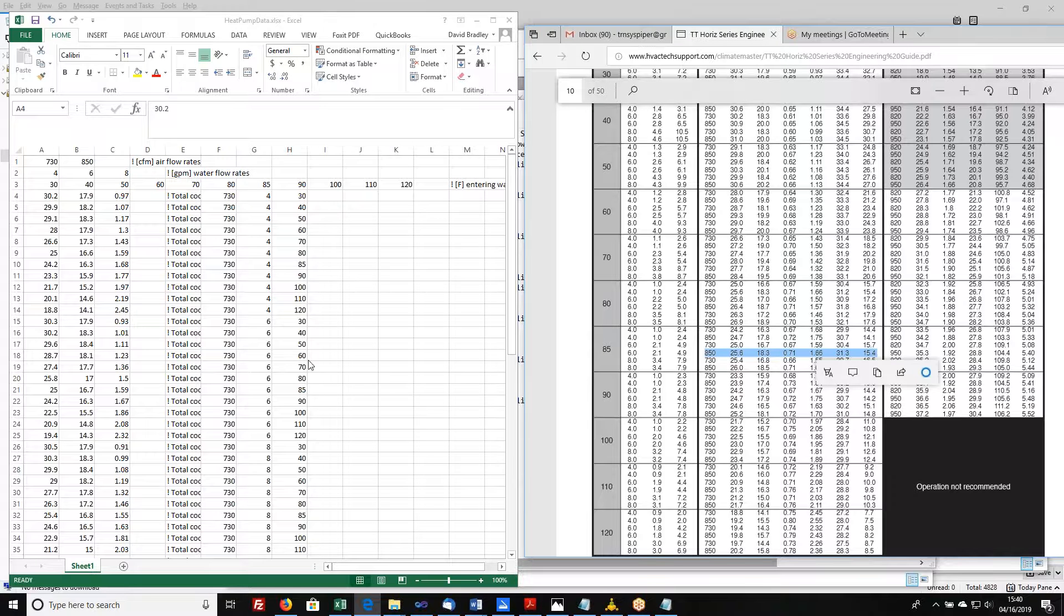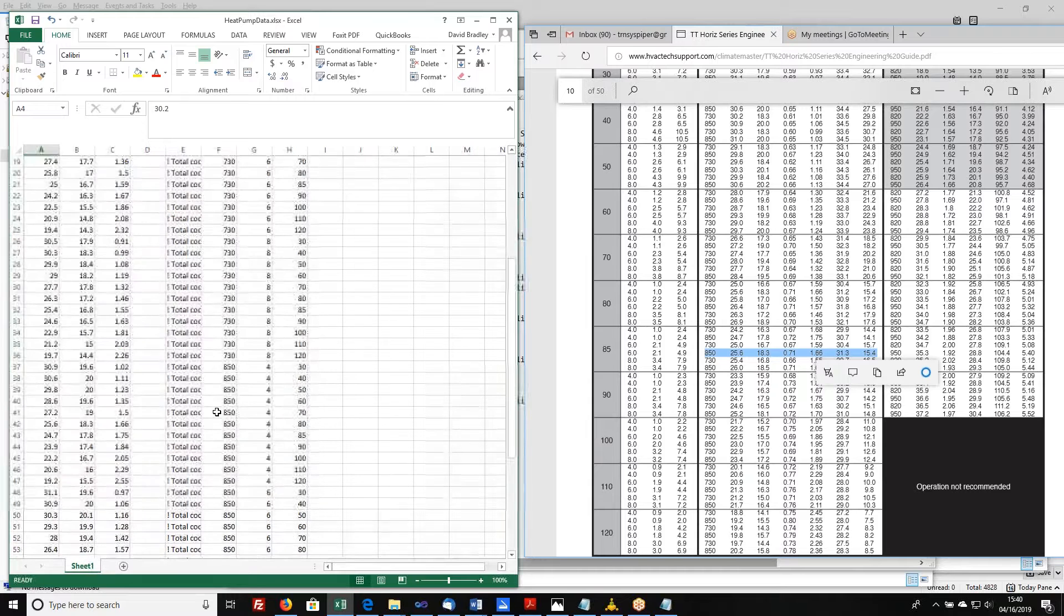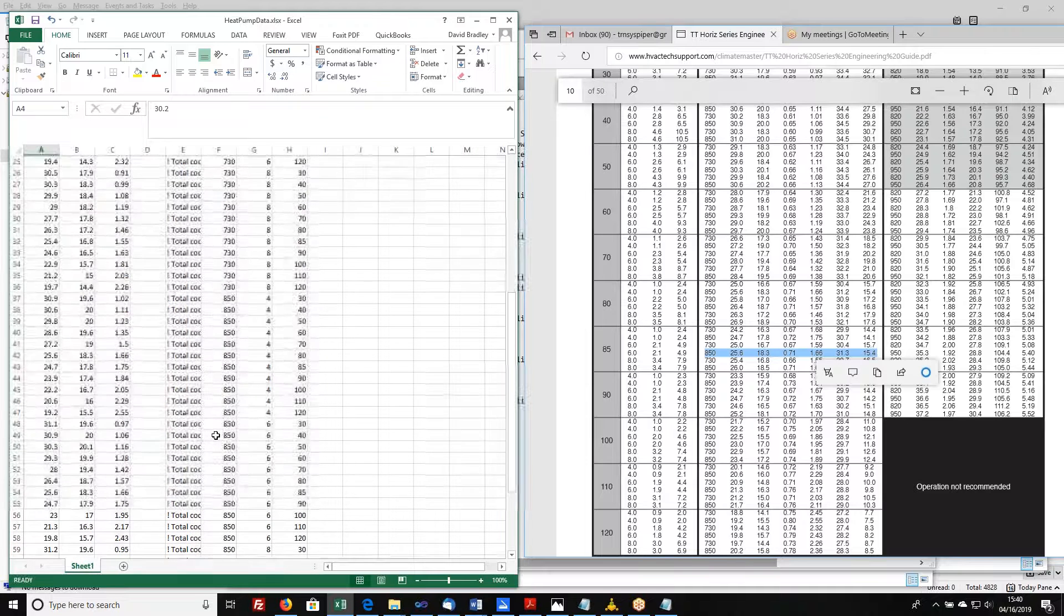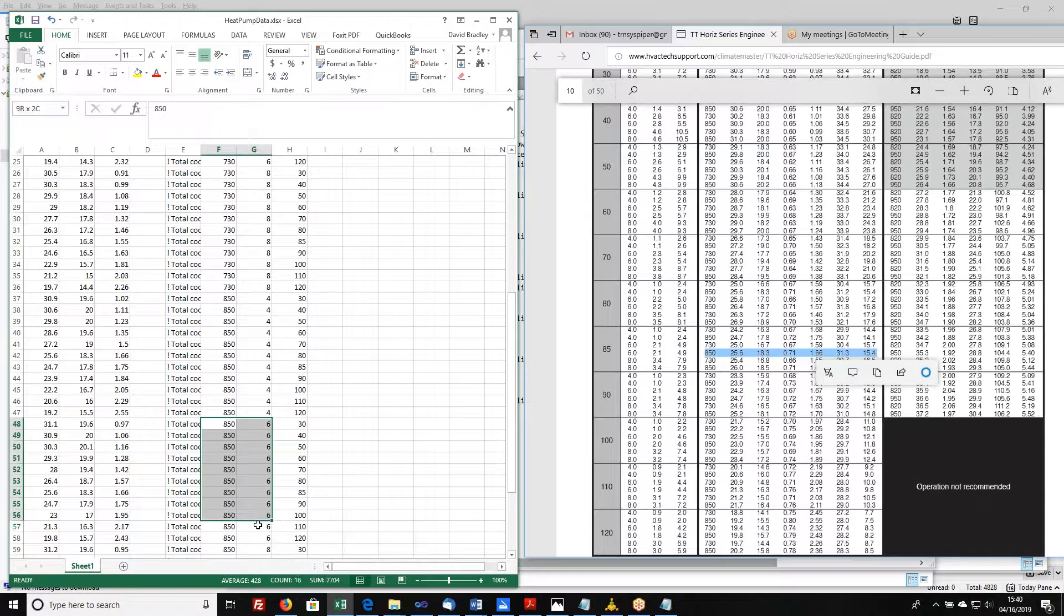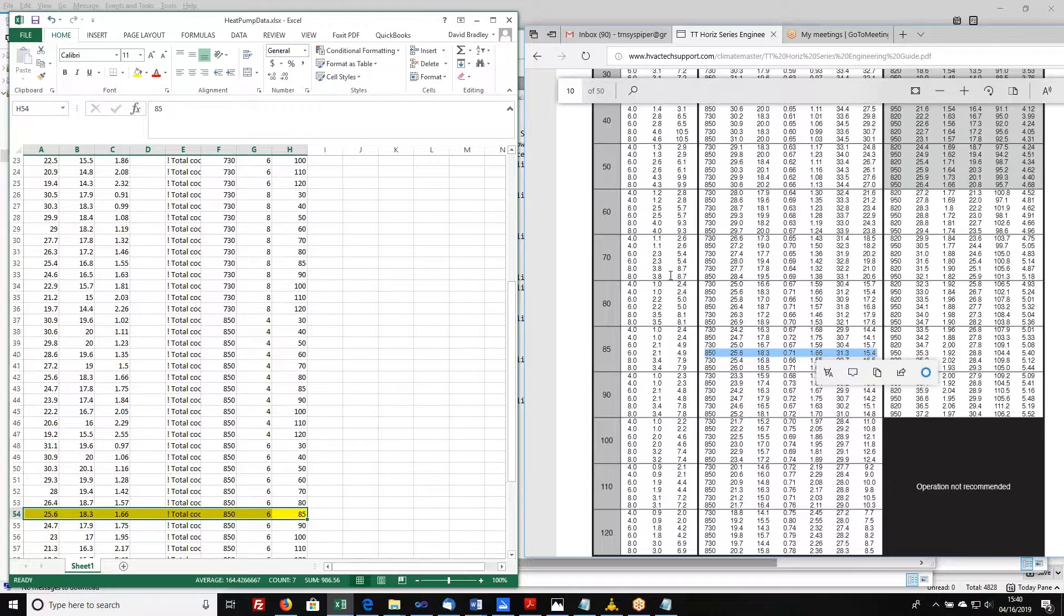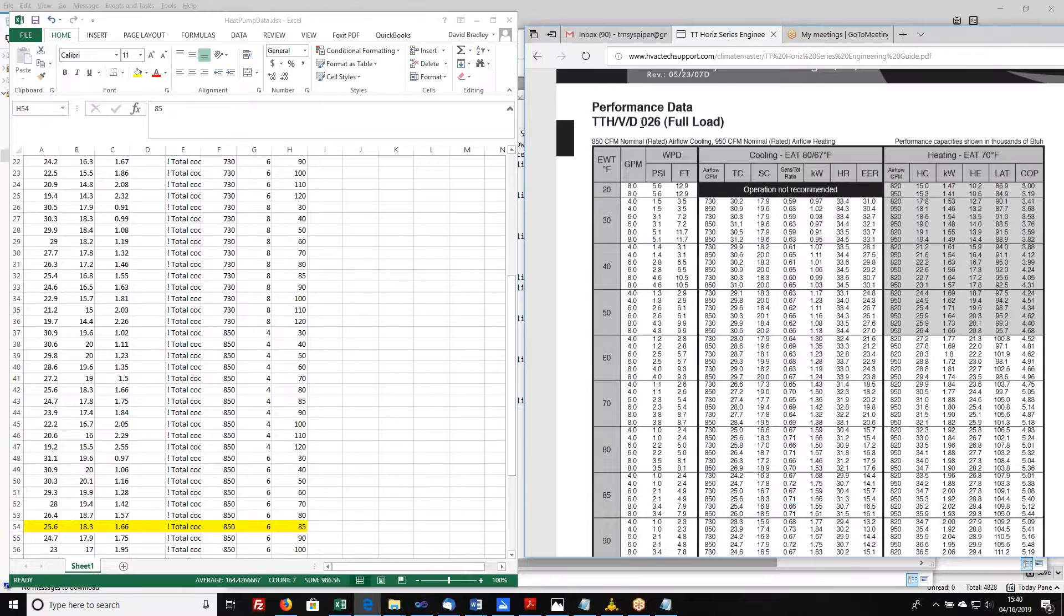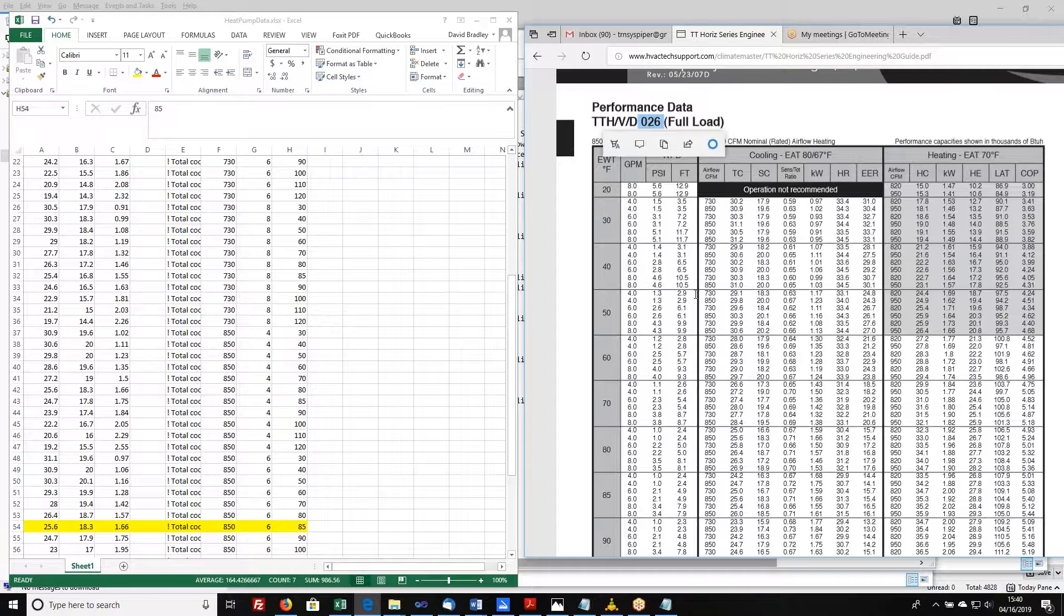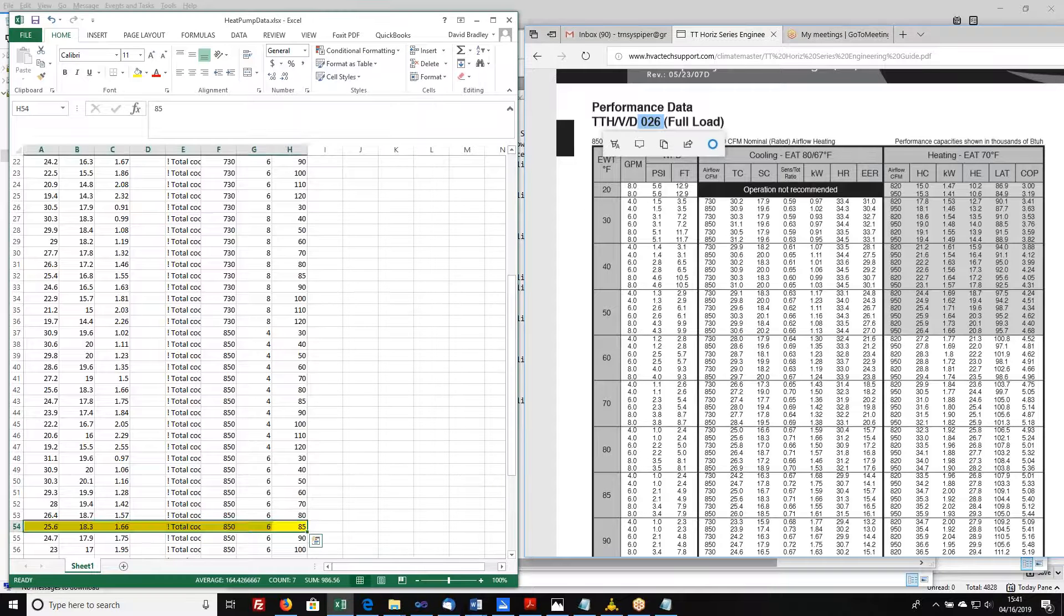So I need to find that same point in my data file. So I'm looking for 850 CFM. I'm looking for 6 GPM, somewhere in here, and I'm looking for the 85 points. Right there is my rated condition. A good way of double checking is that if you look at this data file here, you'll see that this is a model 026, meaning that it's a 26 kilo BTU per hour heat pump. And you see that their cooling capacity at the rated condition is pretty darn close to what they call it for the model number. That's a pretty good guess that you've got the right spot.